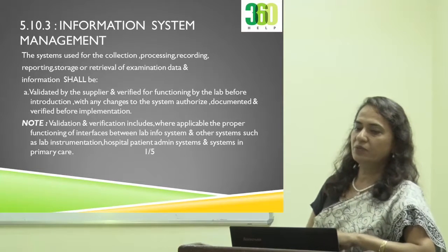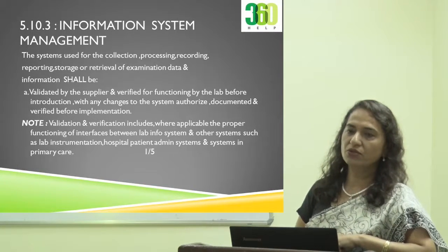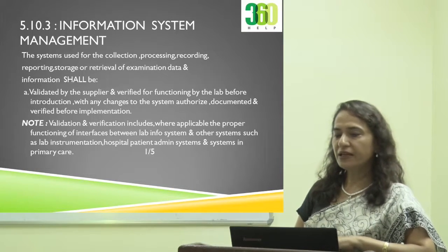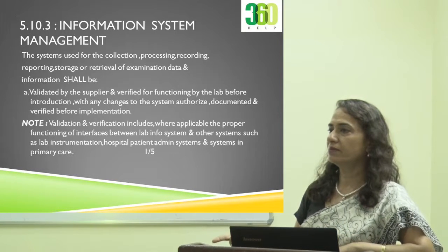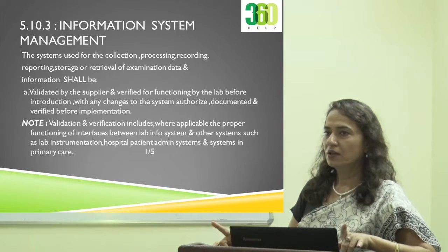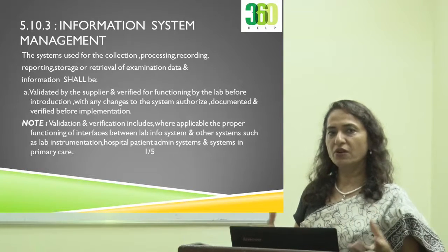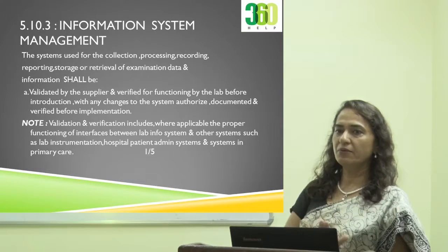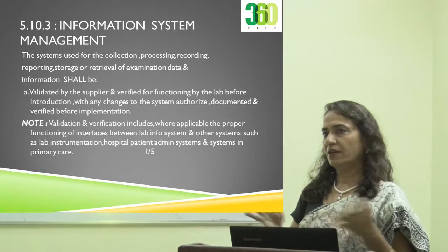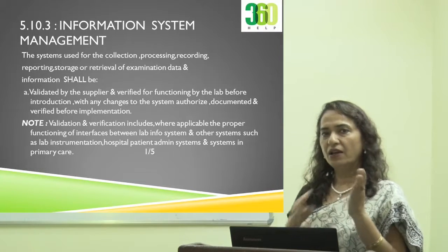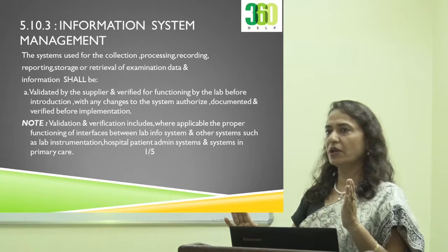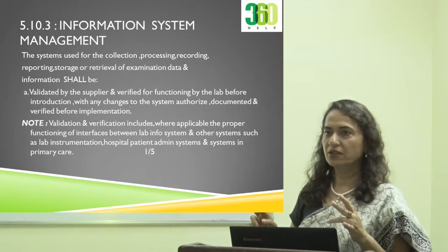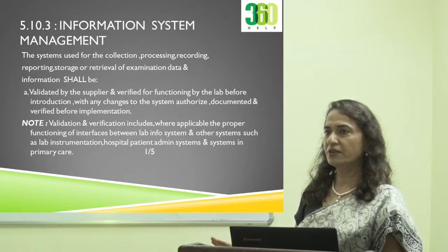System used for collection, processing, recording, reporting, storage, retrieval of the examination data and information shall be validated by supplier, verified by the lab. Again, same terminology. Once they are creating the software, they will validate everything, how it functions. When it comes to you, you will run dummy patients, verify. If it is interfacing, you will verify. Urea is going against urea, creatinine is going against creatinine, neutrophils values are not changing, they are properly getting interfaced.